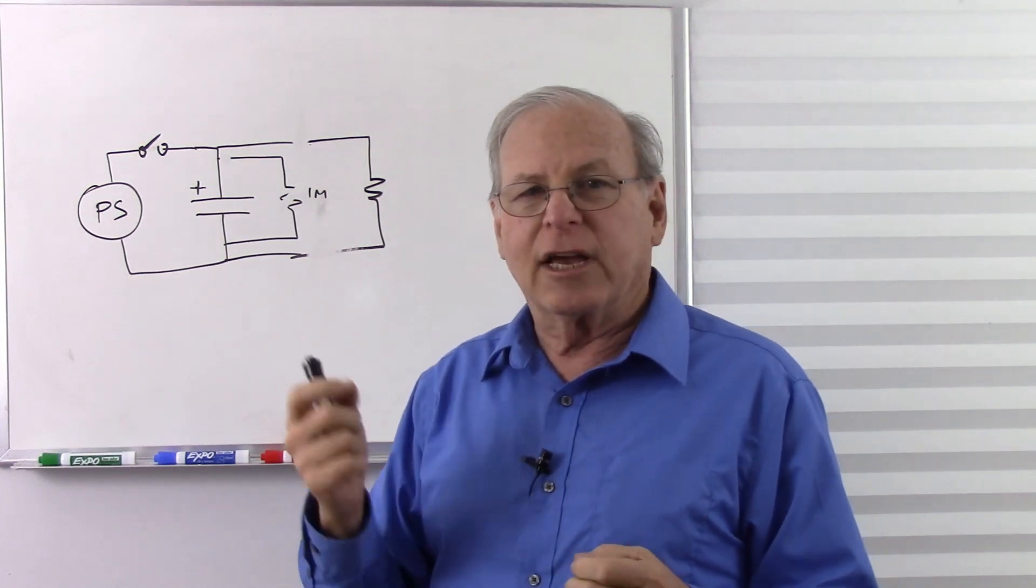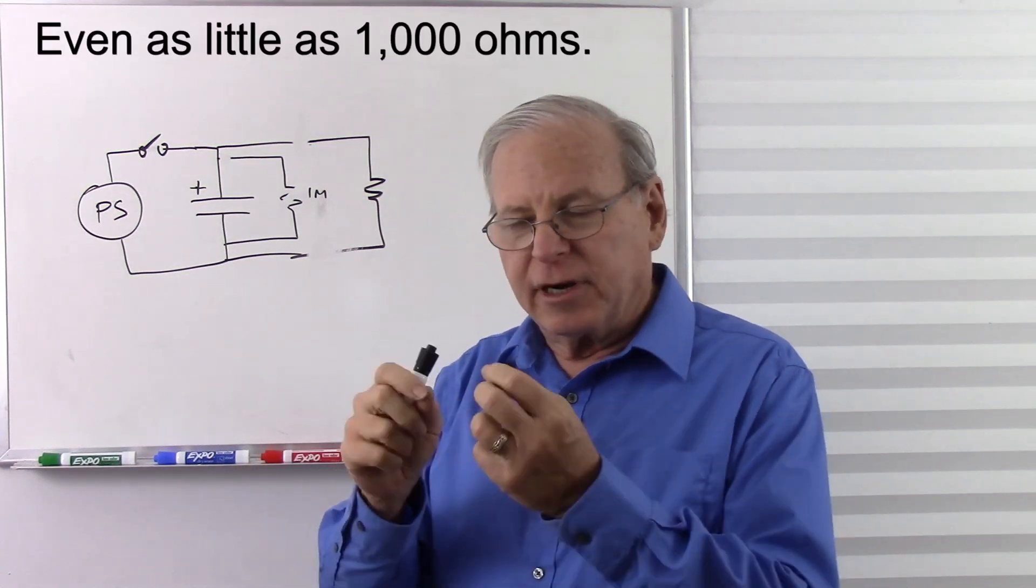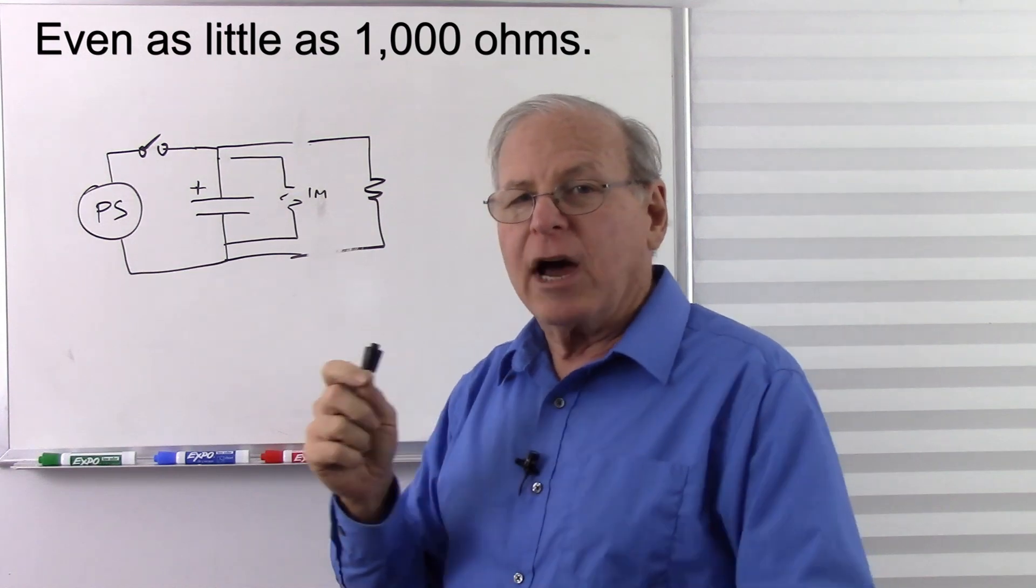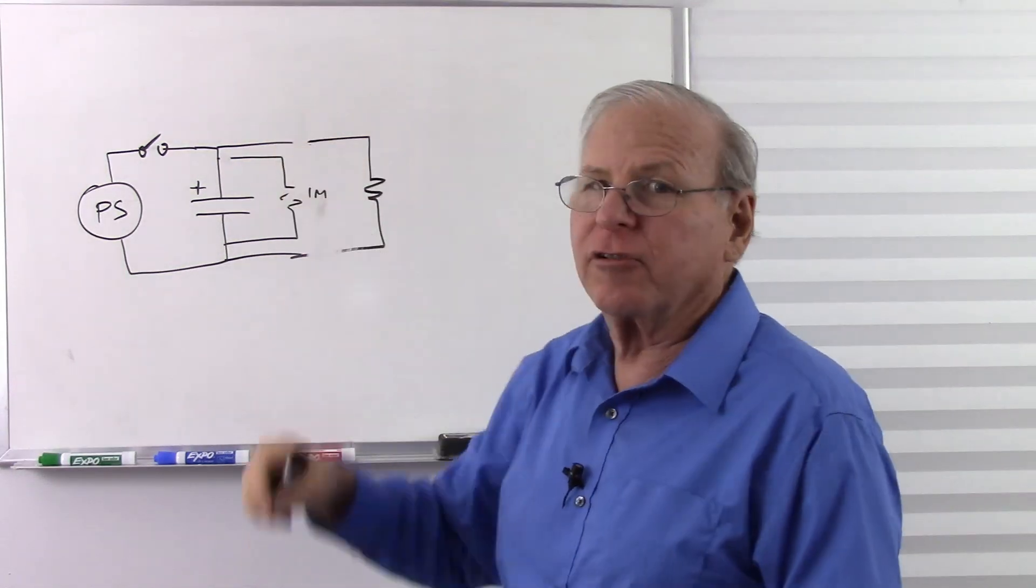How are we going to do that? The quickest, easiest way is to take a big resistor, maybe 100,000 ohms or a megaohm, put it in a clip lead, clip the opposite end to ground, and touch that to the top of all the capacitors to make sure they're discharged.